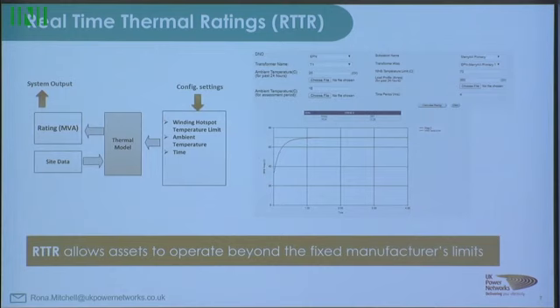One of the big benefits of rolling this out is that we can defer some unnecessary upgrades of the network, because if we know we can push our transformers a bit harder, we don't have to upgrade them as often. Another benefit is if one transformer in a substation fails, we can push the remaining transformer harder for a short period, depending on the situation, instead of putting customers off supply. So ultimately this allows us to operate beyond the fixed limits.